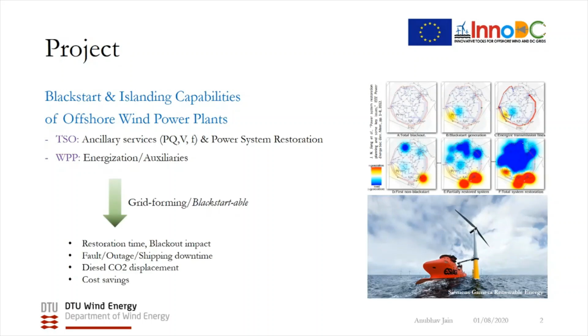Grid forming wind turbines or black startable wind turbines can allow wind turbines to participate earlier in the power system restoration, because now the wind turbine doesn't need to wait for the network reconstruction to finish, but can instead act as a black start unit to provide green, high power, fast black start, and also defend against potential cascaded blackouts by doing trip to house load or controlled islanded operation. This ultimately reduces the restoration time, the unserved load, and thus the overall blackout impact, leading to cost savings.